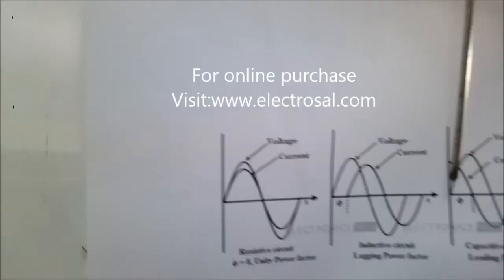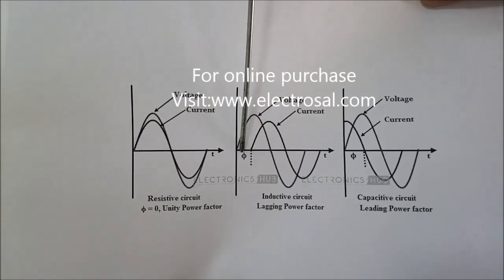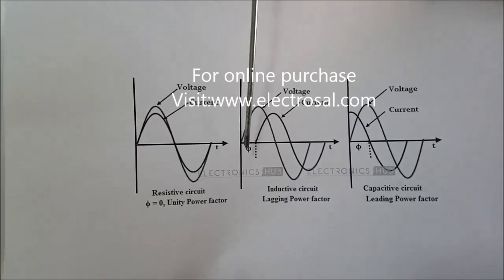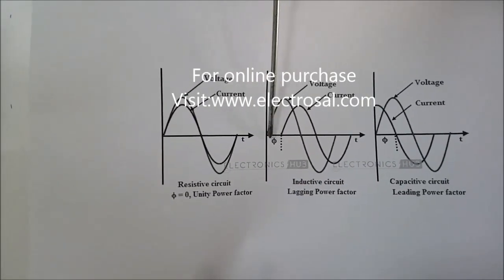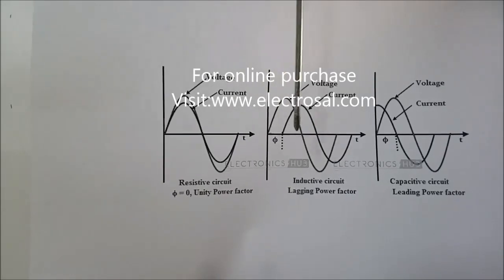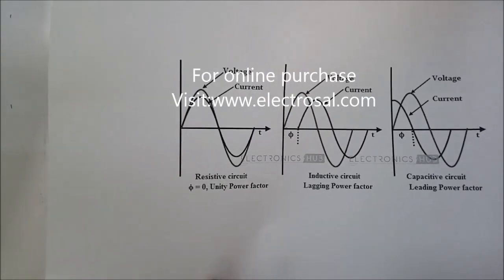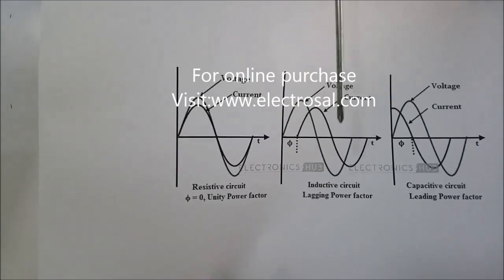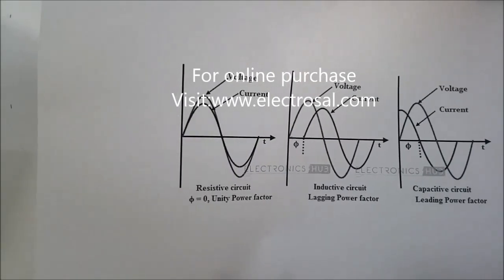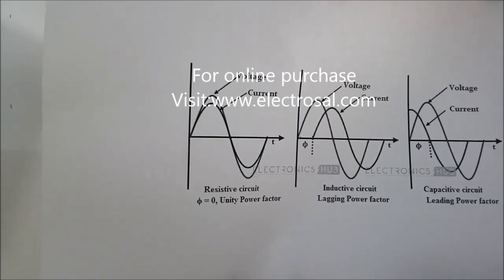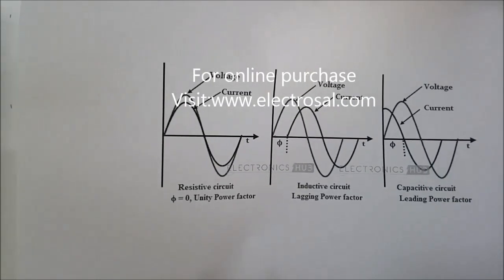Now we will see the waveform. The time difference was 3.03 milliseconds initially. The current waveform was lagging by 3.03 milliseconds, and now it has improved and shifted to 1.36 milliseconds, which means the current waveform has shifted closer to the voltage waveform.